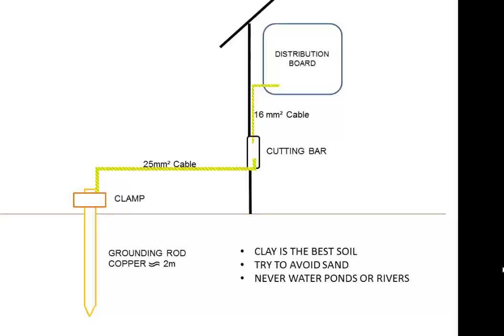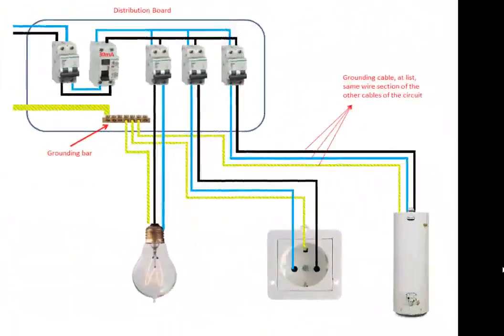The grounding rod should be made out of copper, if possible, and be around 2 meters long. This rod is connected to the structure through a 25mm square cable. This cable is connected to a cutting bar and then to the electrical distribution board. This cutting bar allows us to disconnect the grounding rod for inspection or making grounding tests safely. Inside the distribution board, the cable coming from the cutting bar is connected through the grounding bar to all the grounding wires of the different secondary circuits.